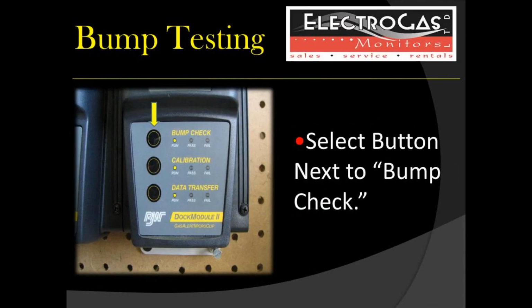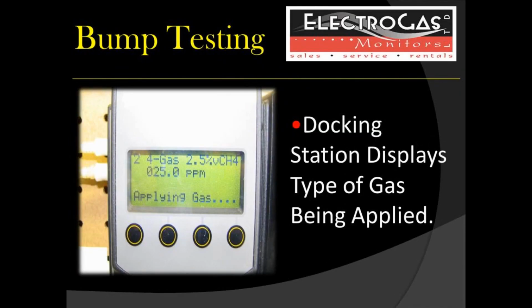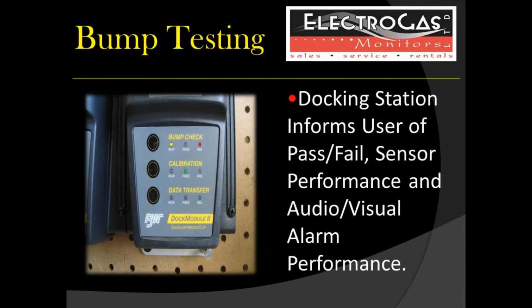To perform a bump test of your monitor, press the button next to the bump check on the test module. The display of your docking station will then show what type of gas is being applied. The docking station will show you whether your monitor passes or fails, while the display shows sensor performance as well as audio and visual alarm performance.